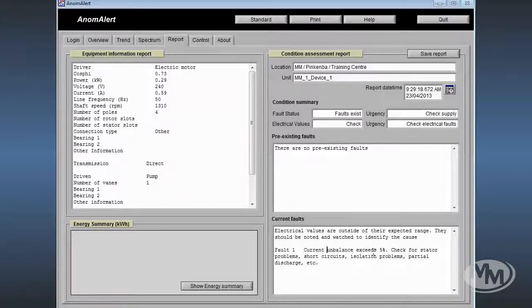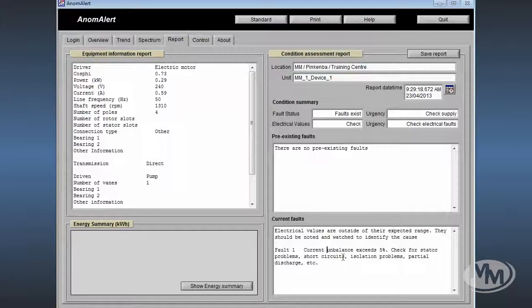It recommends to check for stator problems, short circuits, insulation problems or partial discharge. It can be seen that short circuits is identified as a probable cause. This is accurate as a short circuit was deliberately introduced into the test machine.